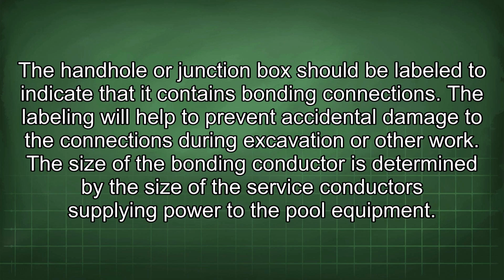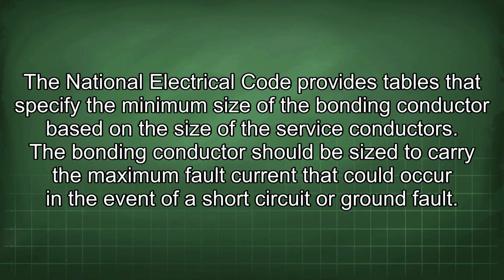The size of the bonding conductor is determined by the size of the service conductor supplying power to the pool equipment. The National Electrical Code provides tables that specify the minimum size of the bonding conductor based on the size of the service conductors. The bonding conductor should be sized to carry the maximum fault current that could occur in the event of a short circuit or ground fault.